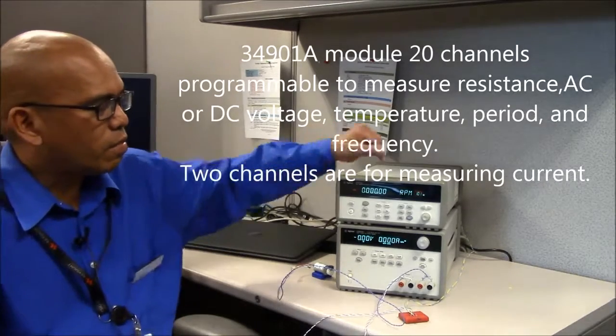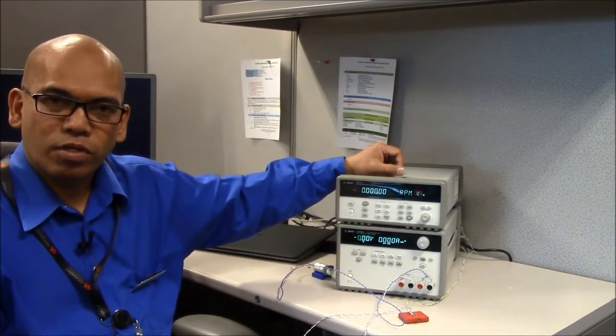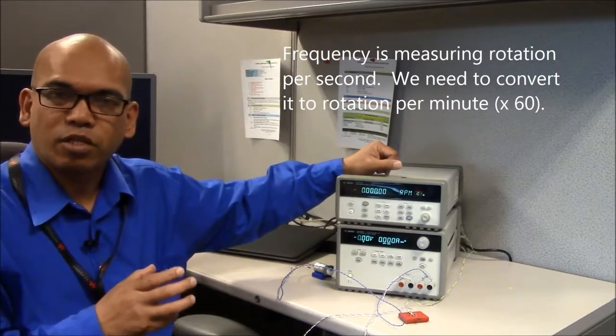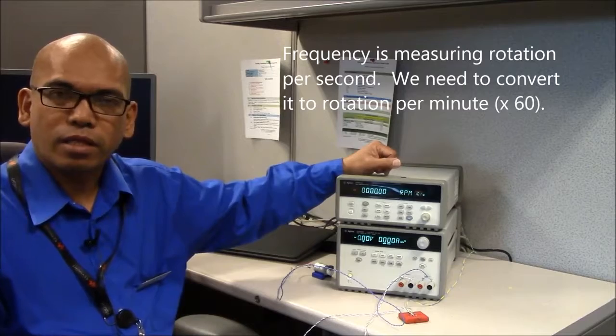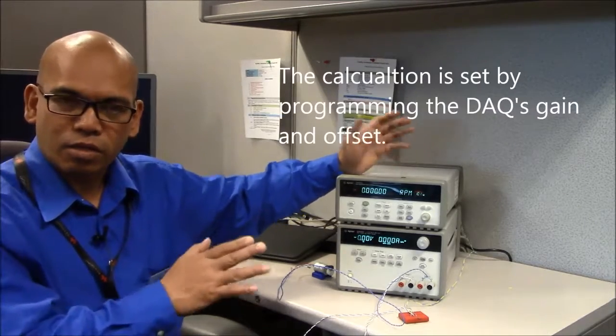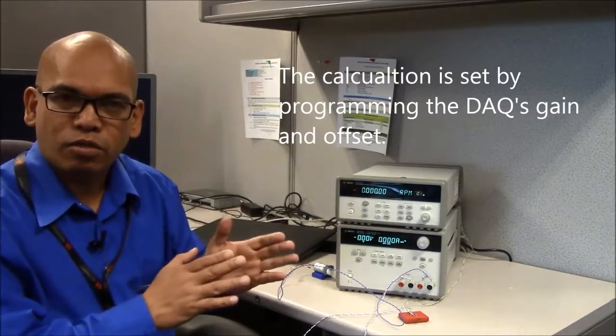In this demo, we're using the frequency and I'm going to program that to reflect RPM instead of cycles per second. To do that, we need to multiply the gain by 60 because that converts it from seconds to minutes.